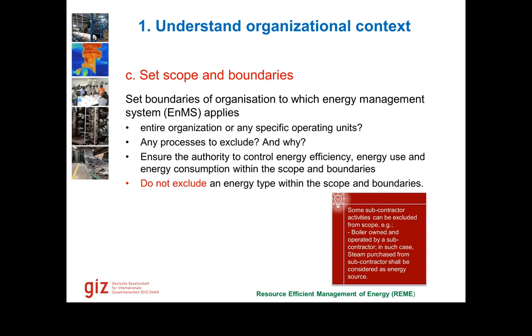They said, because the boiler is operated by a contractor. For a moment, I thought, yeah, since the boiler is being operated by the contractor, we could exclude that. But when I did the scoping visit, I went to the factory and I saw the boiler. The boiler was inside the facilities, not outside the facility. It was very nearby their machines and their engine hall. And the boiler was very inefficient and very unsafe. The boiler safeties were taken off. It was causing a lot of smoke, and the health and safety conditions at the boiler area were very bad.